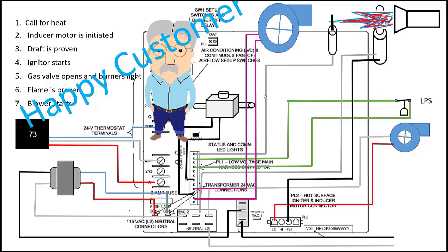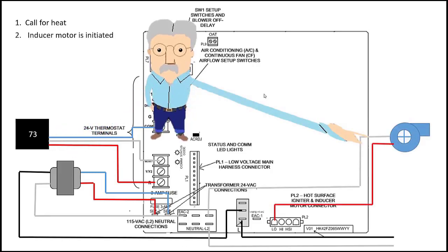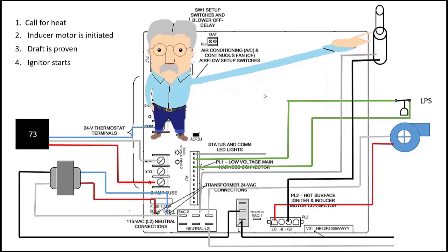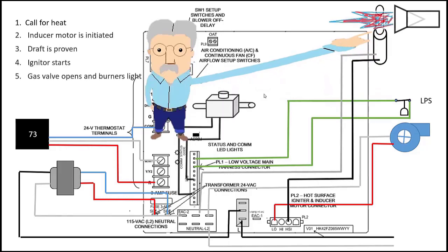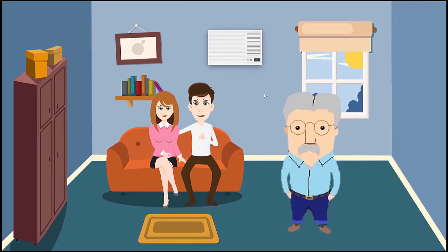That is our basic sequence of operations for a furnace. So let's quickly review. We have power to our circuit board and there's a call for heat. Our draft inducer fan starts. Draft is proven. The igniter starts. The gas valve opens and we have flame. Flame is proven. Our indoor blower starts. And we end up with a happy customer.